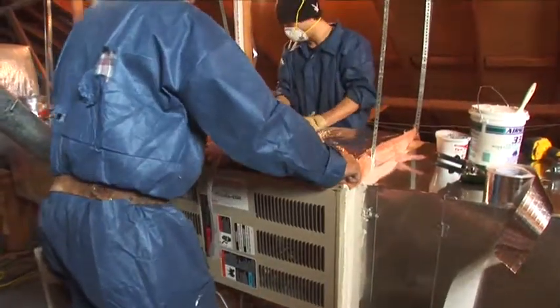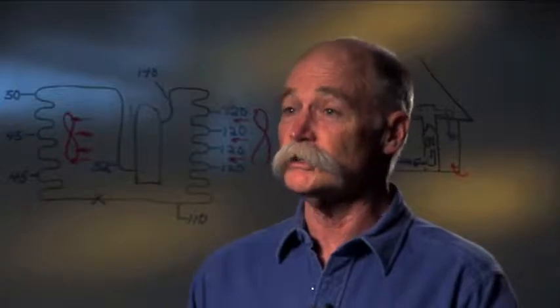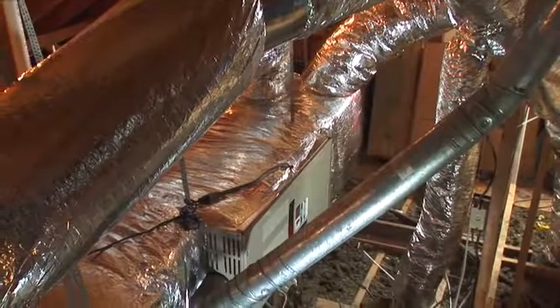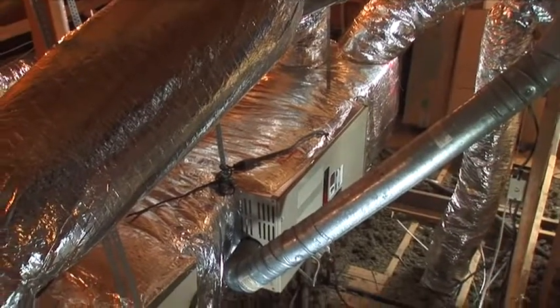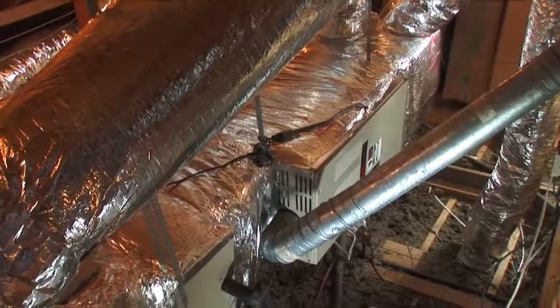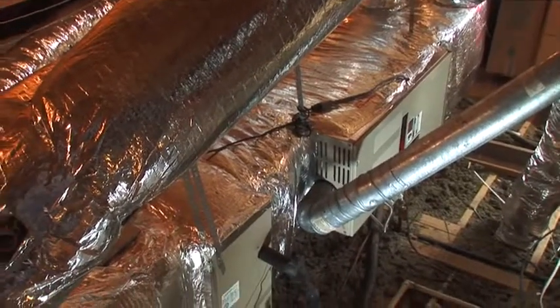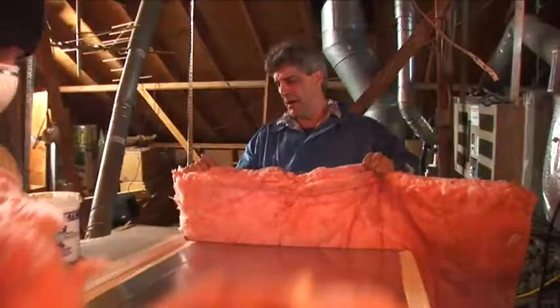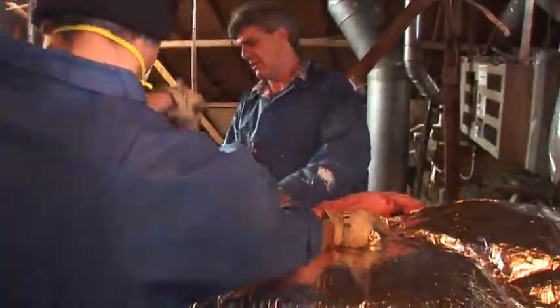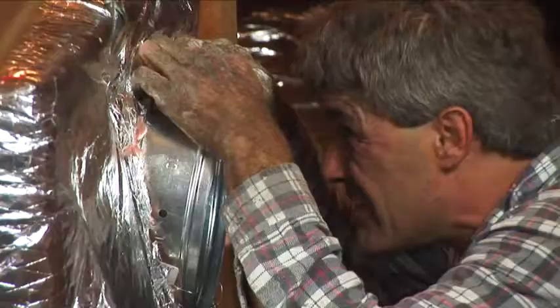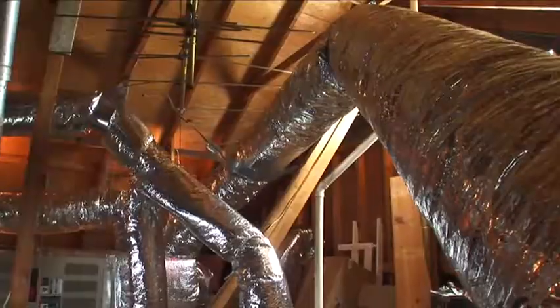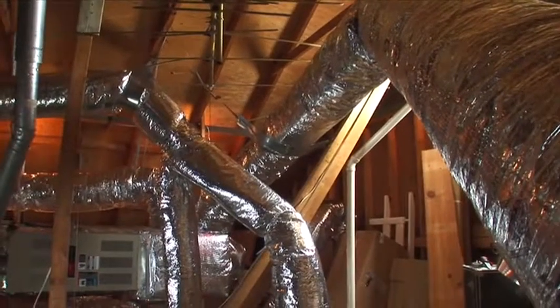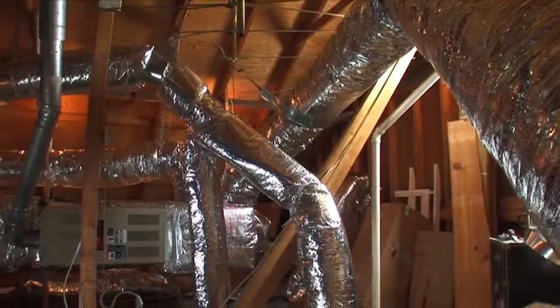It's too restrictive, it's too leaky. The most duct systems are an absolute mess. So there's a good number of houses out there that what some people should do is just take them out and start over. A totally new duct system is better in every way. No leaks, thicker insulation, and cleaner. It's also properly engineered so that it can move the right airflow. This makes the system quieter, and it gets the air properly balanced to each room.